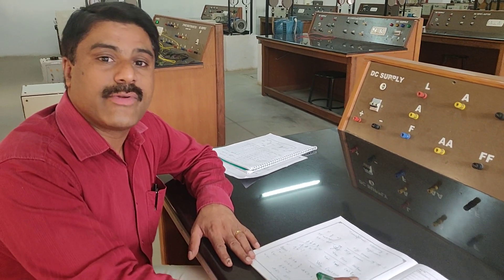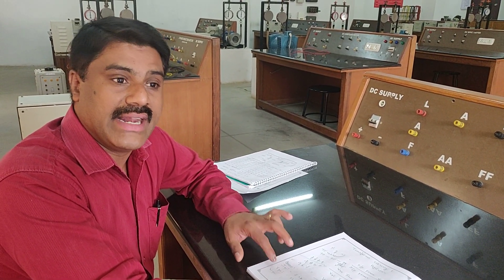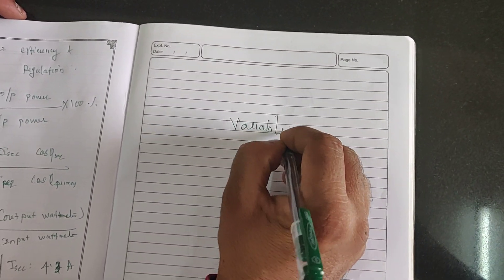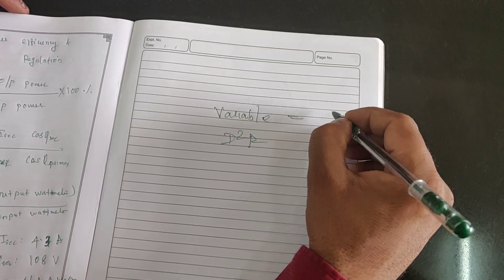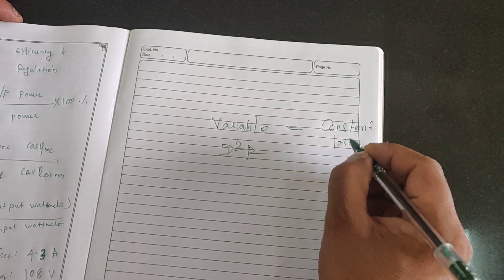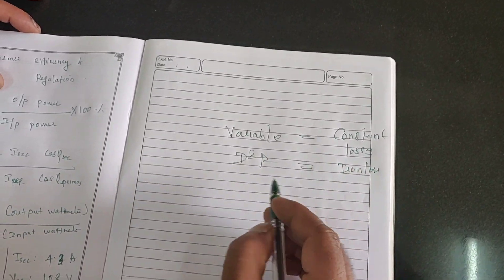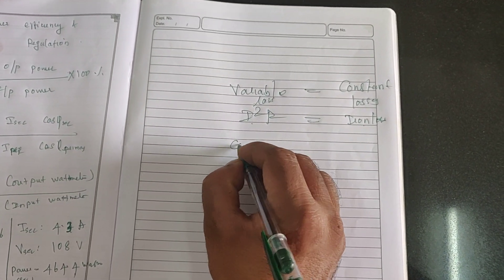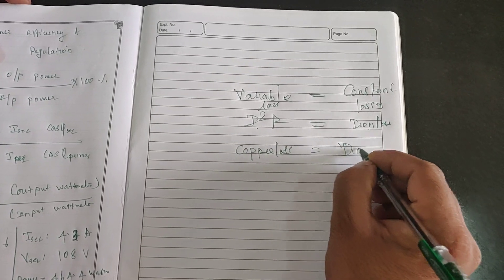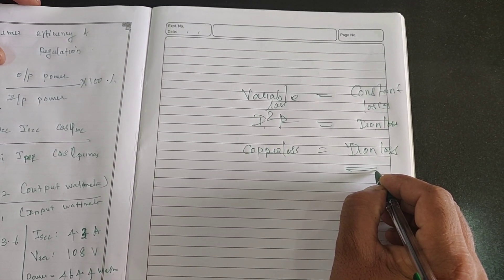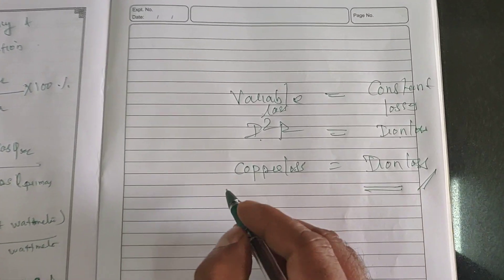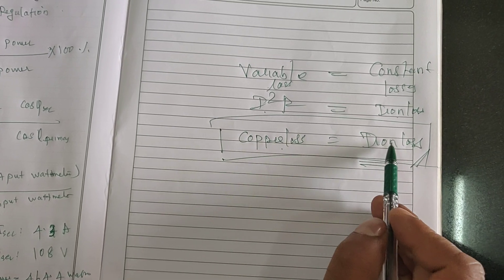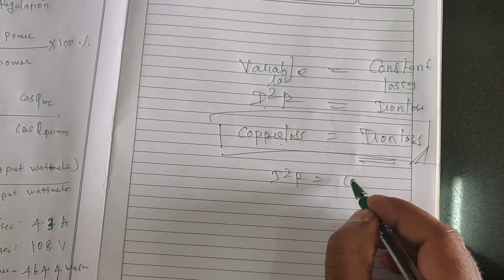A transformer will deliver higher efficiency when its losses satisfy a specific condition. The variable losses — that is, I²R losses (copper losses) — should be equal to the constant losses (iron losses). So to simply conclude: when copper loss is equal to iron loss, a transformer will deliver maximum efficiency. This is a common interview question — at what condition does a transformer deliver maximum efficiency? The answer is: copper loss = iron loss, or I²R loss = constant loss (at no-load conditions).